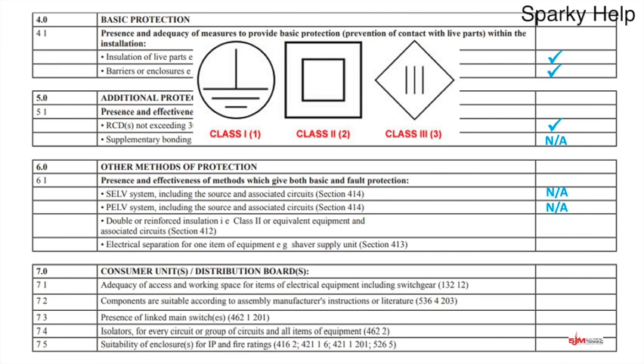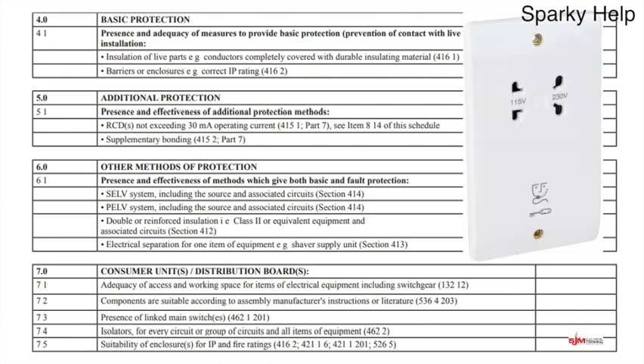So the chances are you may well have installed some equipment that would be class 2. But it could also be part of an installation, hence it refers back to section 412 of the regulations. Electrical separation for one item of equipment, e.g. a shaver supply unit. Well, I'll put it up anyway, but this is a shaver socket. Shaver socket, it's not SELV.